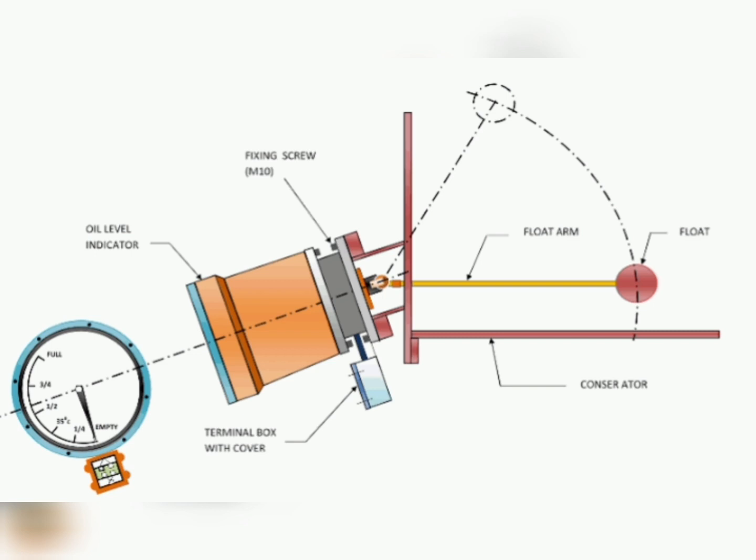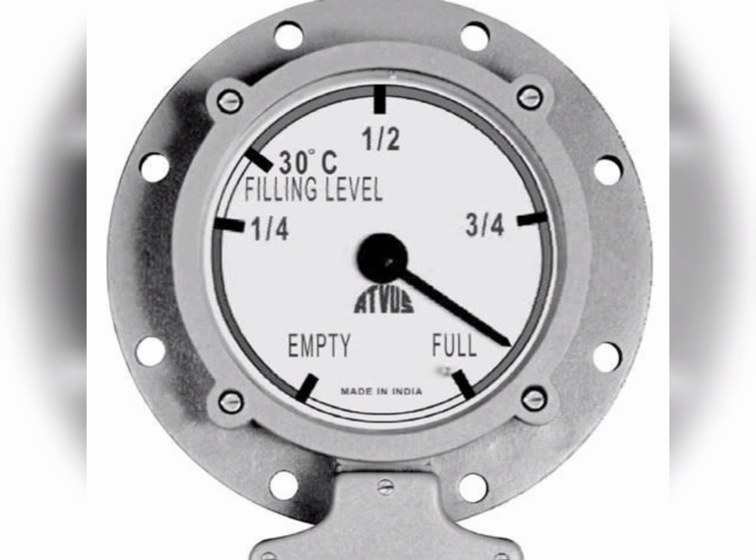The MOG operates by using a magnetic float suspended inside the transformer tank, connected to a magnetic sensor that detects the position of the float. When the float moves up or down with the oil level, the sensor sends a signal to the gauge or indicator, which displays the oil level. The MOG can also be connected to an alarm or trip mechanism that interrupts the flow of electricity to the transformer when the oil level is too low, preventing damage caused by lack of oil. It is common practice to install the MOG in combination with other protection devices such as an oil surge relay and pressure relief valve.